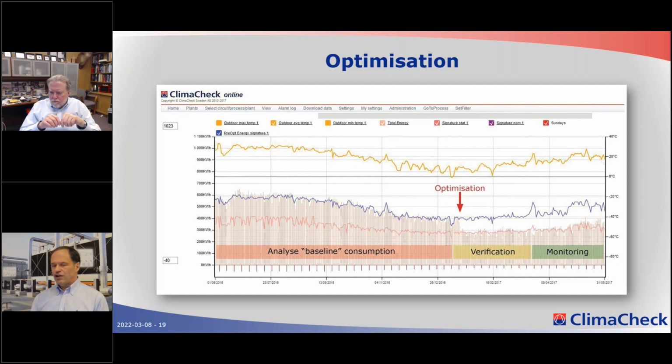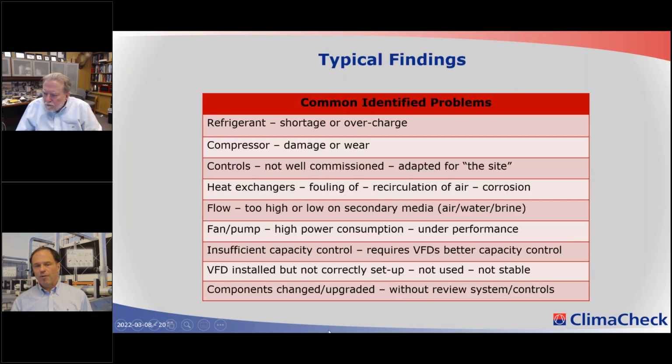If I have a deviation in the energy signature, but I do not have a change in performance, then I've changed my load. So it helps a lot with troubleshooting. And that, I think, is the key to bring data together so you can cost effectively pinpoint the problems.